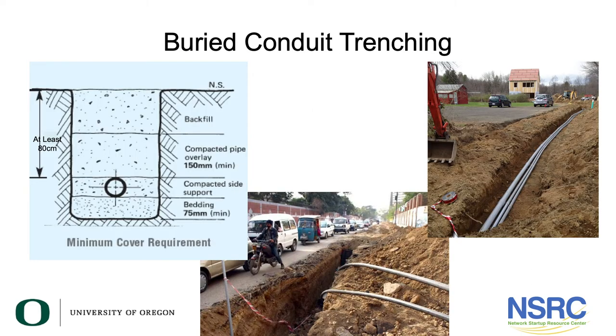Here are some photos of conduit being trenched and laid — this looks like it might be in India or South Asia, given the tuk-tuk in the lower picture. The cross-section on the left shows the proper method: dig the trench about one meter deep. If there are a lot of rocks, put down some bedding material, then lay your pipes, cover them with dirt without big rocks, and then backfill with native materials which may include larger rocks.